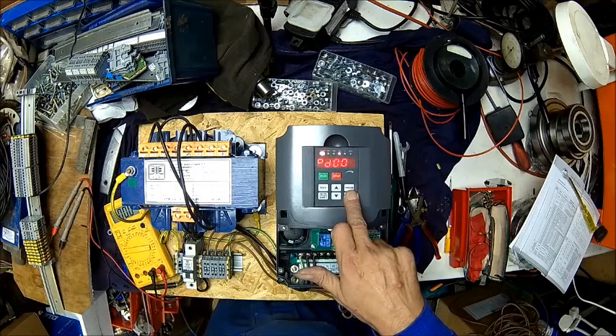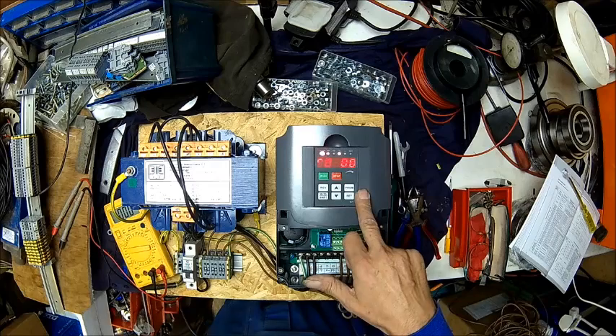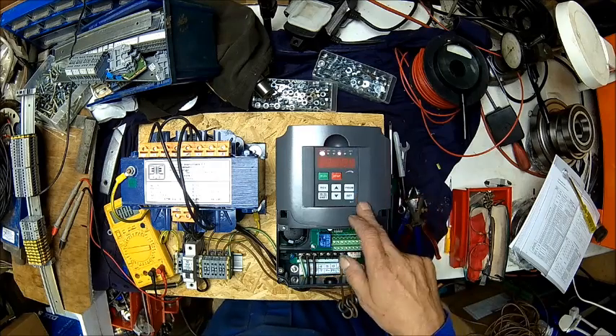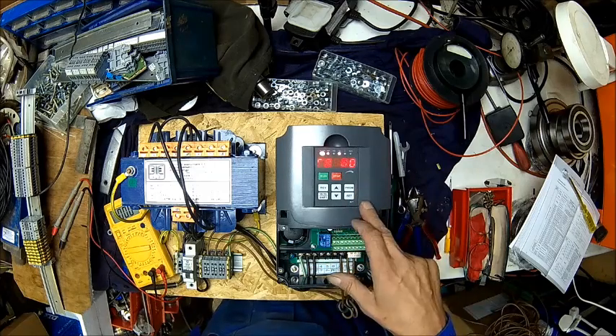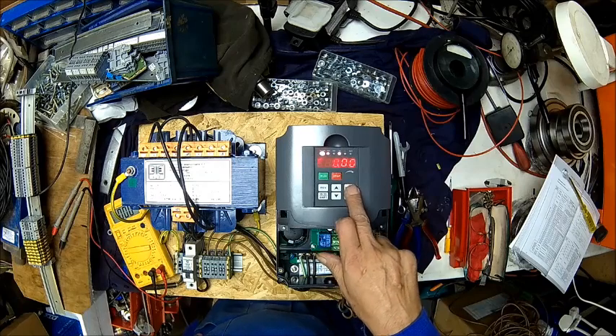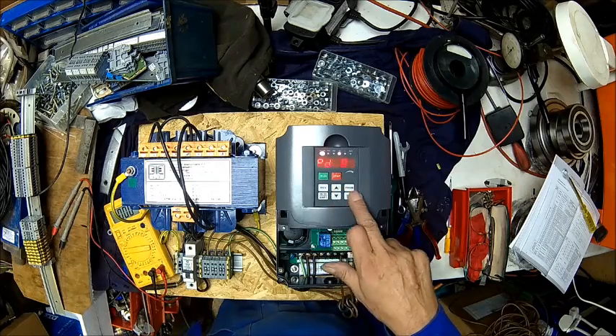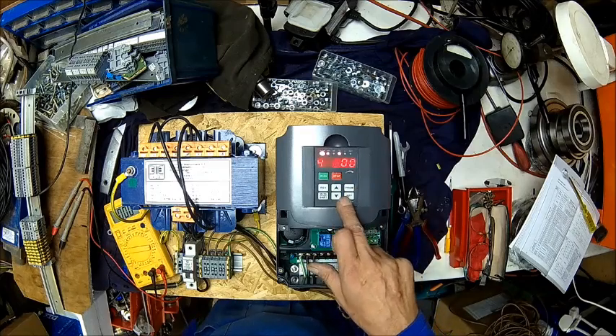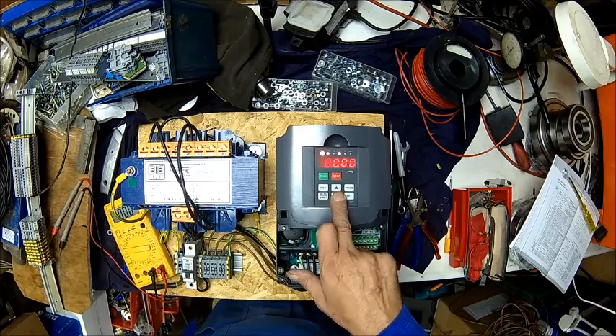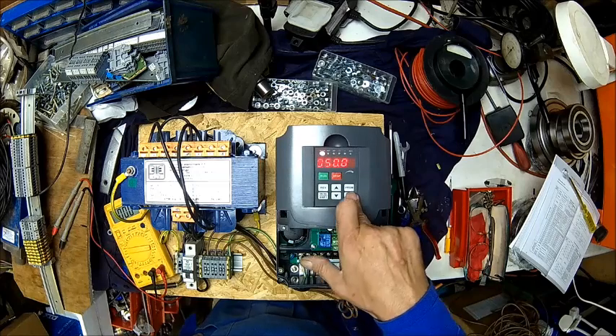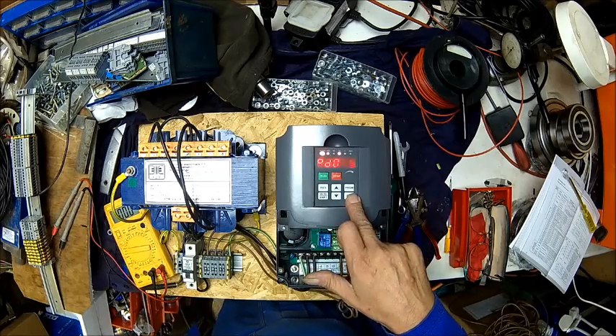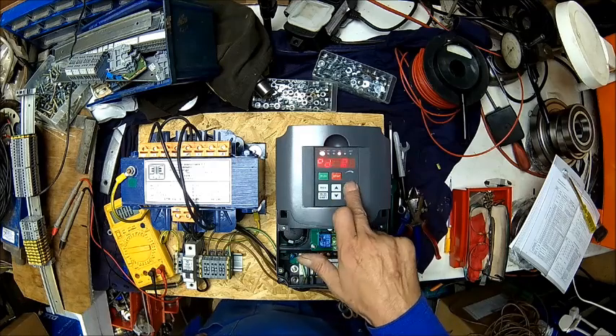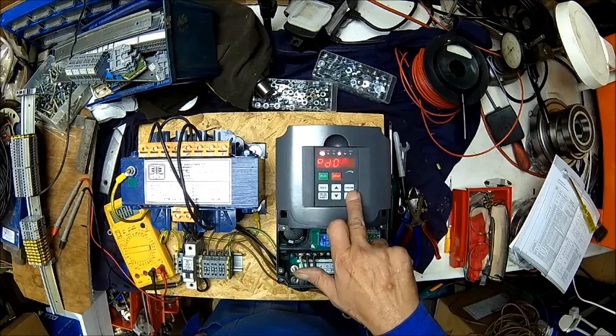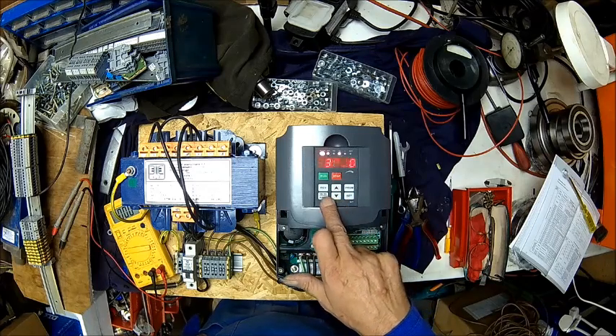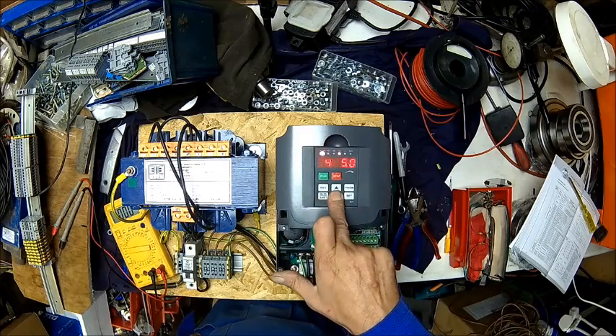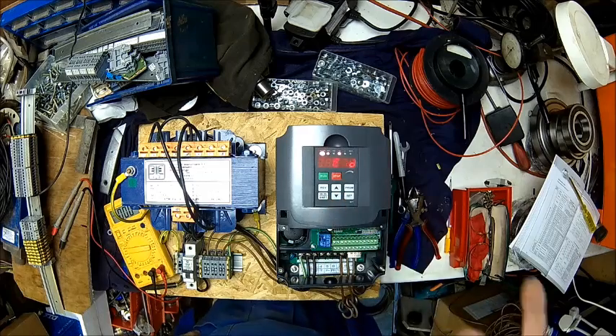So our base frequency is 50 Hertz. That's parameter 4. The base frequency is the frequency we want full voltage, and in this case it's 50 Hertz because he wants 50 Hertz, 415 volts. So that's parameter 4, base frequency, and we want to set that to 50 Hertz. So that's set. Maximum voltage is parameter number 8, so we need 8, and at the moment that's set to 380, we want 415. So I guess this motor is 415.